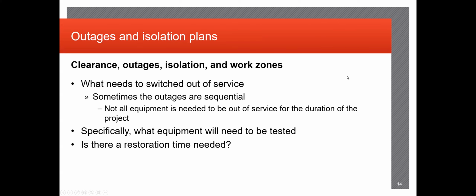So moving on to the outage and isolation plans. Primarily when you're beginning an outage, you need to specifically identify what equipment is going to be placed out of service to ensure that the work that you guys are going to be doing is going to be adequate and it's not going to cause any inadvertent trips or possible injuries, stuff like that. So sometimes weird things can happen. Outages can be sequential, and the client, usually for monetary purposes, will only take out one piece of equipment at a time, so that you're not taking out an entire substation or even an entire feeder to customers, because that can also put a lot of strain on the load for other sites as well.